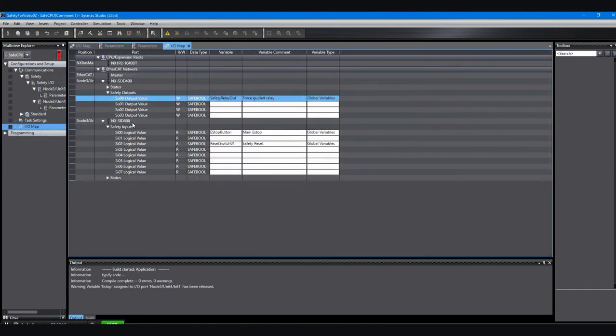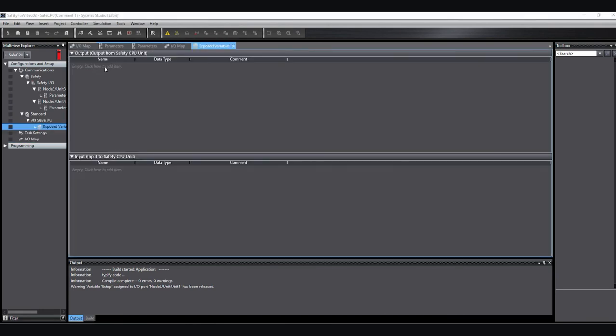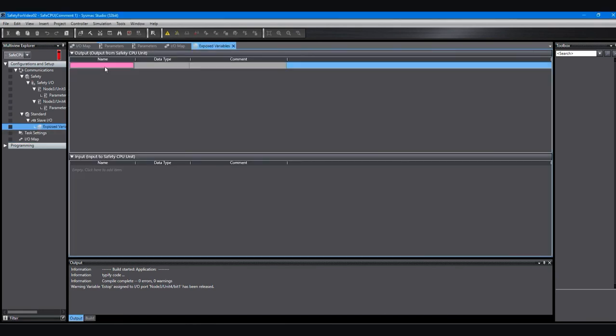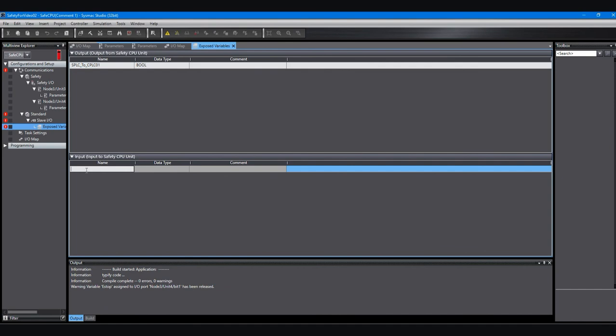Next we're going to create some input and output variables that can be read and written by the control PLC. So if you look on the left over there where we've been clicking around for the regular safety IO, you'll see there's an entry called standard and then underneath that is exposed variables. So we'll open the exposed variables and you can create an output variable or an input variable. So I'll create one at the top there that says safety PLC to control PLC and make it a boolean. That's going to be an output variable. And then I'm going to create an input variable that's going to be the control PLC to the safety PLC. These names are meaningless. It's just to show you the direction that they're going.